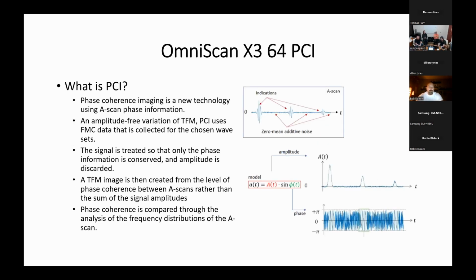One of the big things about the X3 and one of our main selling points on it is PCI. So what is PCI? Phase coherence imaging is a new technology using phase information. It's an amplitude-free variation of TFM. The PCI uses FMC data that's collected for the chosen waveset. Signals are treated so that only the phase information is conserved and amplitude is discarded. You have a TFM image that's generated from the level of phase coherence between A-scans rather than the sum of the signal amplitudes. Your phase coherence is compared through the analysis of the frequency distributions of the A-scans.